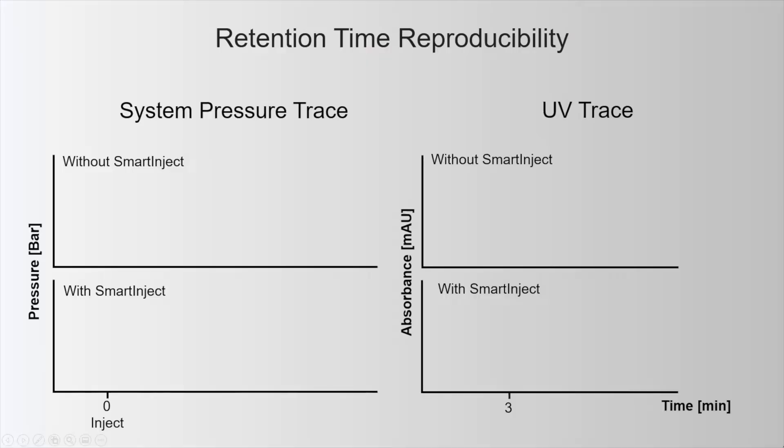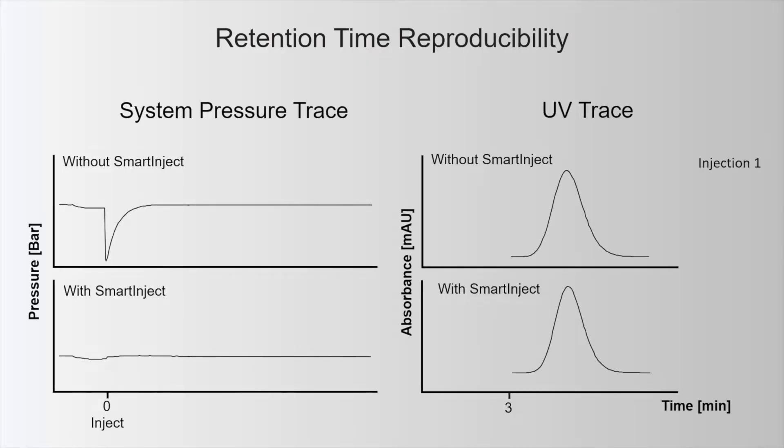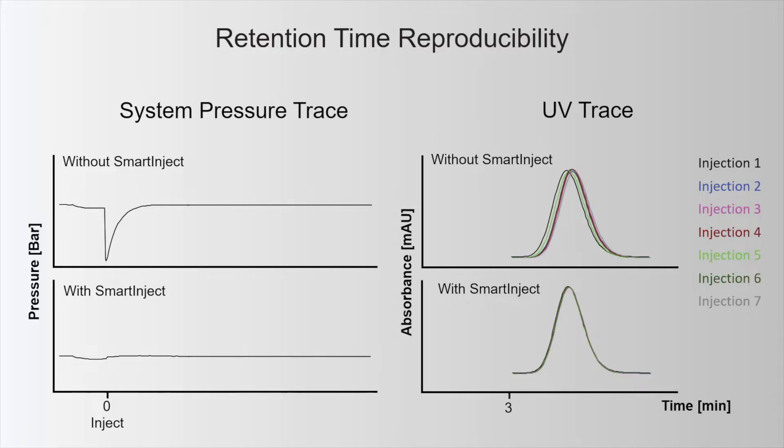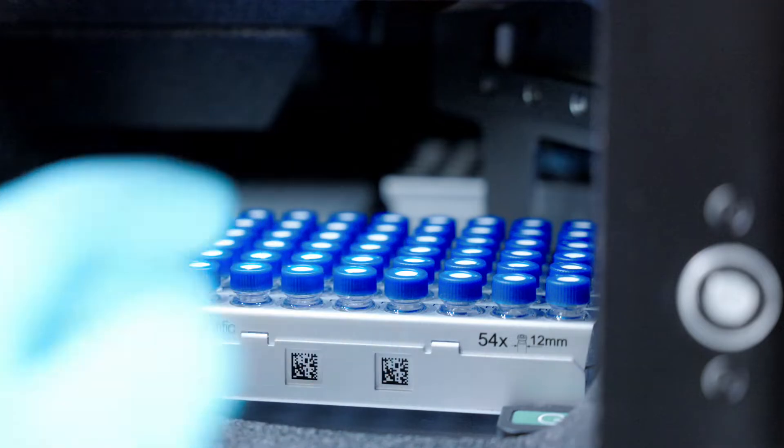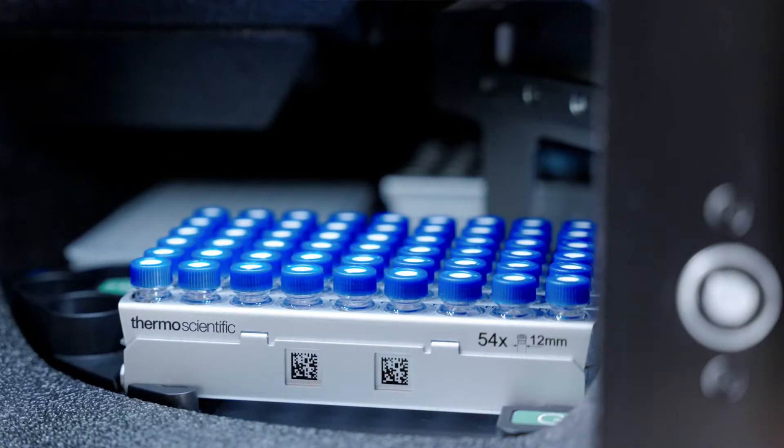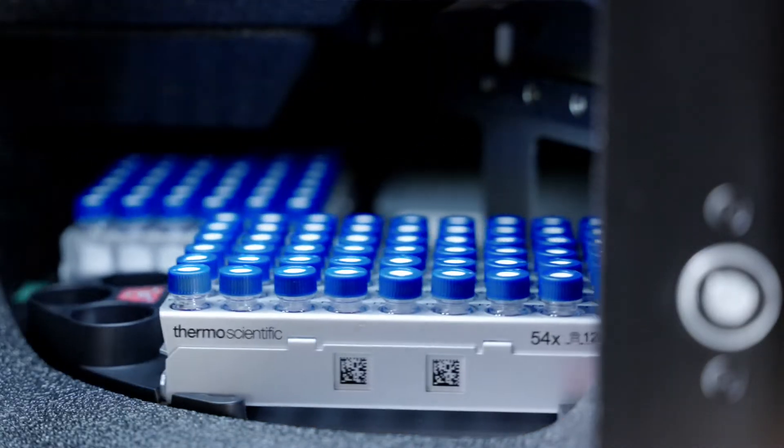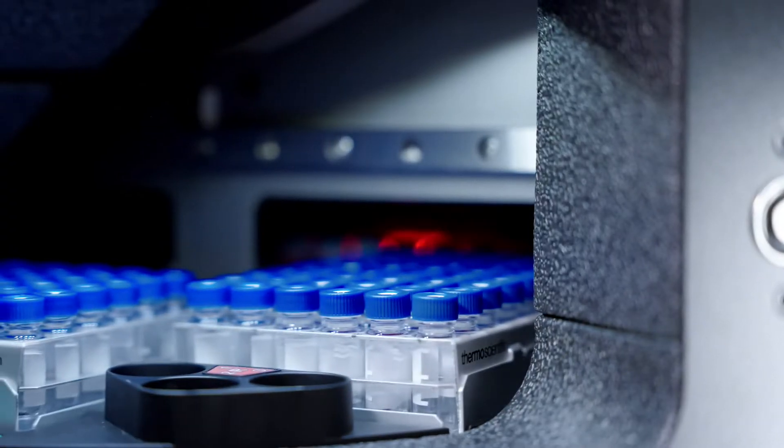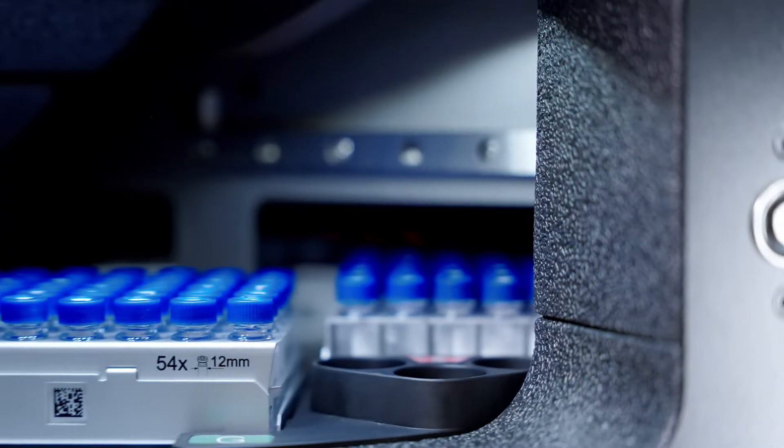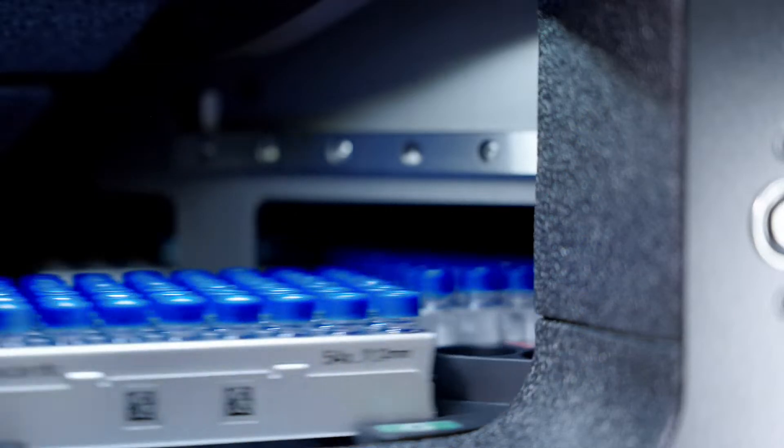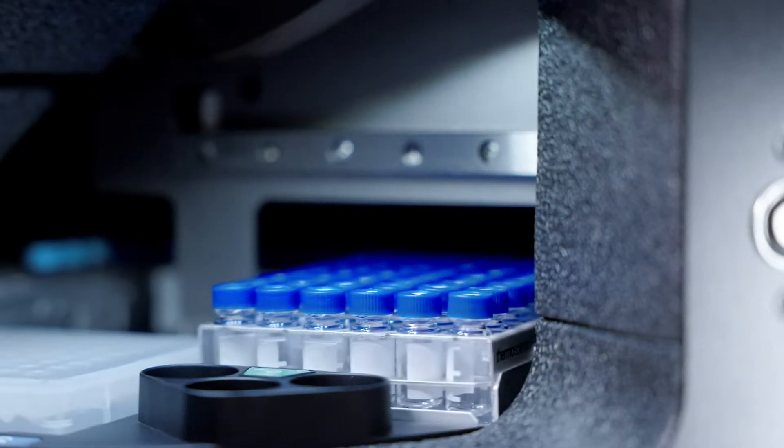SmartInject technology automatically reduces the pressure drop during injection, enhancing retention time precision and extending column lifetime. An automated barcode reader manages inventory by keeping track of sample rack position, orientation and format so you don't have to.